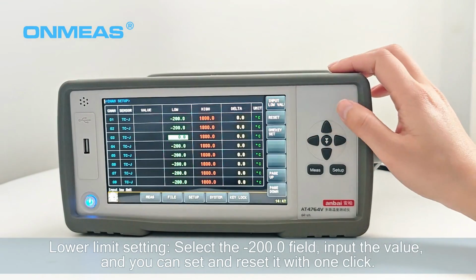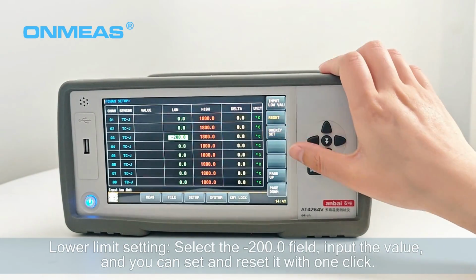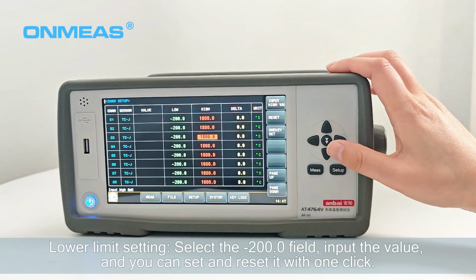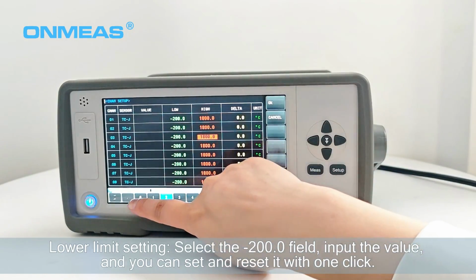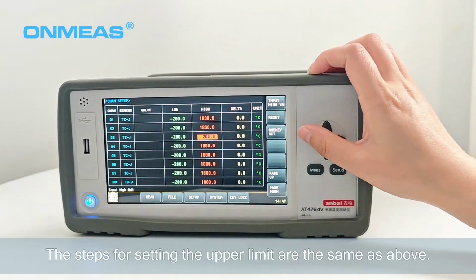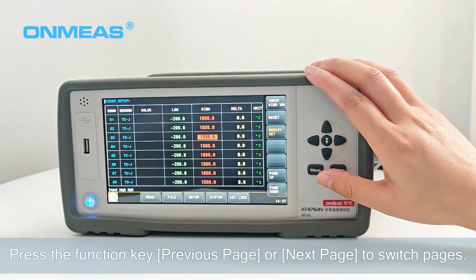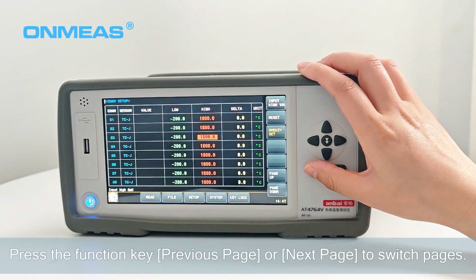Lower limit setting: select the -200.0 field, input the value, and you can set and reset it with one click. The steps for setting the upper limit are the same as above. Press the function key previous page or next page to switch pages.